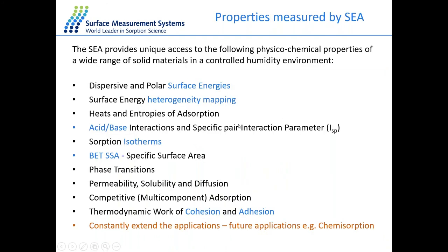The properties measurable with IGC include different components of surface energy using polar and non-polar molecules, as well as surface energy heterogeneity mapping. We can calculate acid-base properties using polar molecules, giving Ka and Kb values. With organic vapors we can determine sorption isotherms and BET surface area of the solid material. From the surface energy, we can also calculate the work of cohesion and adhesion — important in formulation development for determining affinity between materials or how a sample will blend with other components.